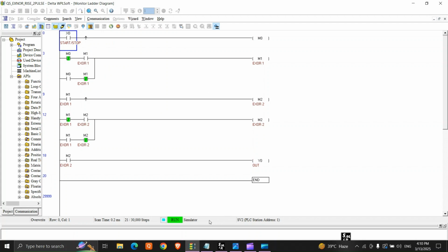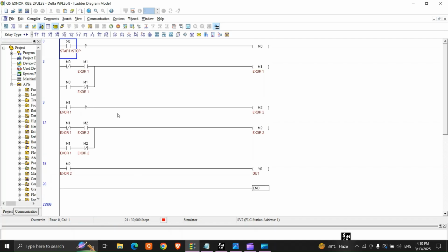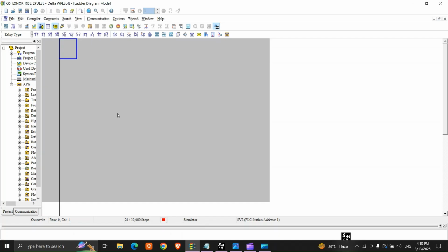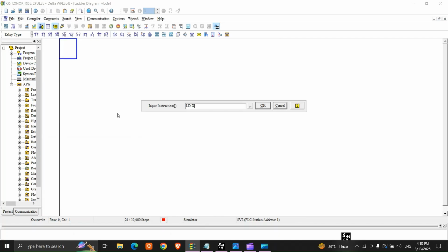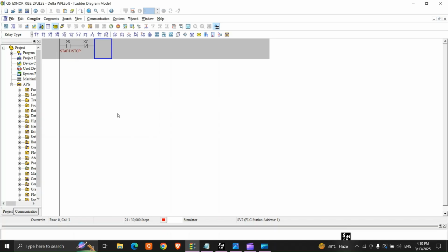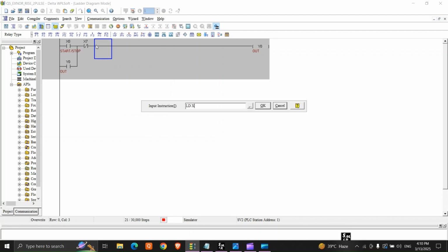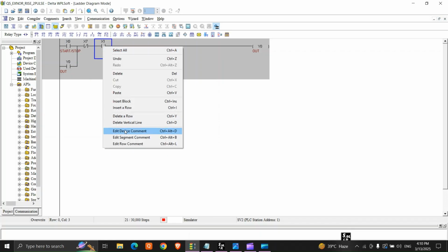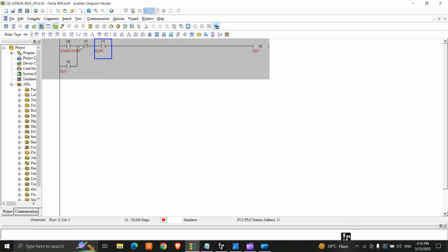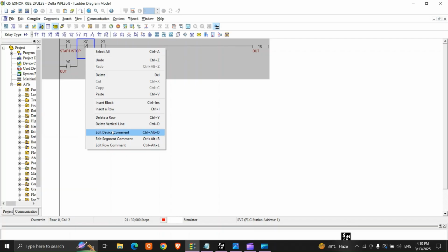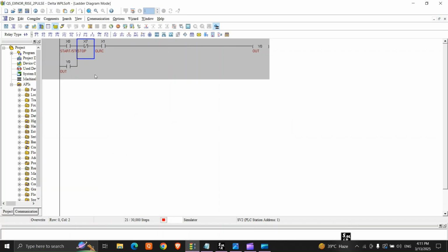Now what we'll do, we'll make a DOL circuit. We'll do LD x0, LDI x7, and we'll use the holding LD y0. So now we'll use this to connect our run, OUT y0, and an OLRC. LD, let's suppose x1. Now our x7 is our stop button, x1 is our OLRC, and x0 is our start button.